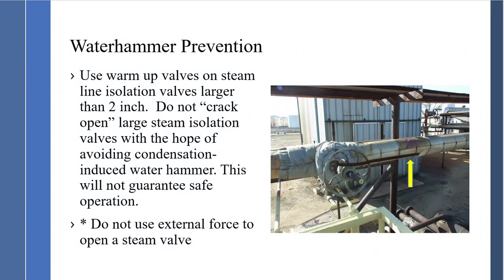Use warm-up valves on steam isolation valves larger than 2 inch. Do not crack open a large steam isolation valve hoping to avoid condensation-induced water hammer — this will not guarantee safe operation. One of the most unsafe operations is people using external forces on large valves to open them. The valve manufacturer did not design the bonnet for that external force, so you risk breaking the bonnet and having a major failure. Don't do this.